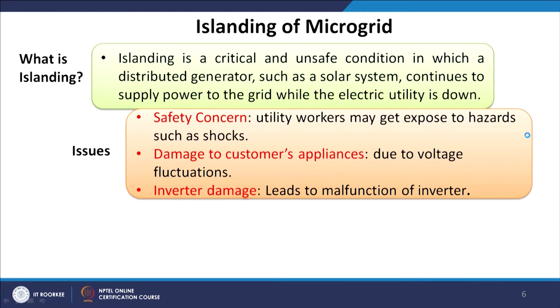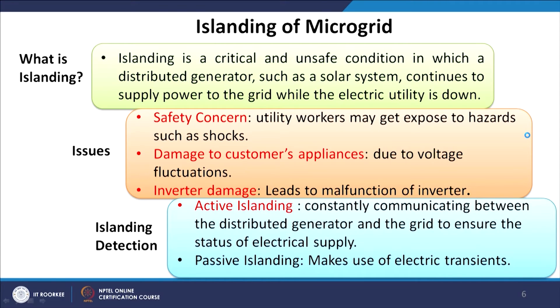The main issues with islanding include: safety concerns — utility workers may be exposed to hazards such as shocks, and damage to customer appliances may occur due to voltage fluctuations, as well as inverter damage and malfunction. Islanding detection is also a concern. There are two major methods: active islanding, which constantly communicates between the distributed generator and the grid to ensure the status of electricity supply; and passive islanding, which uses electric transients to determine whether islanding has occurred.